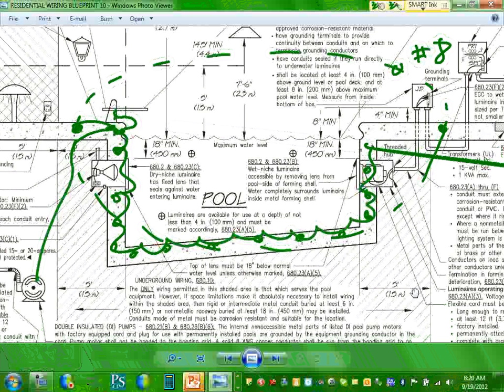So for our project, Joe, all you need to do: 1 GFCI receptacle, like we said yesterday, not closer than 6 feet, GFCI. The pole mounted lights 5 feet away from the swimming pool, GFCI them, throw them in GFCI. The pump itself is going to be on the 20 amp circuit, GFCI that pump. The heater does not have to be on GFCI because it's heating the water somewhere else. But you have to have a disconnect for the pump too.